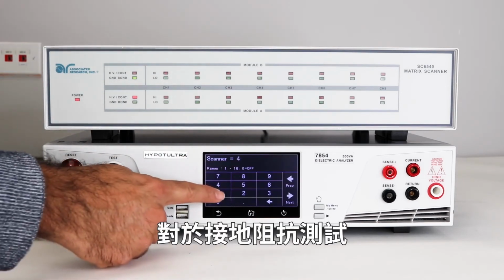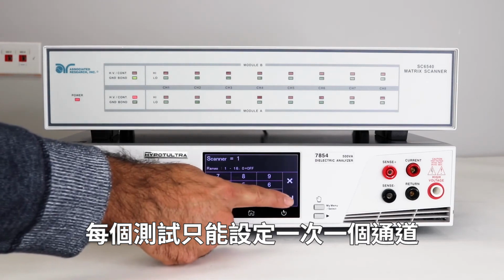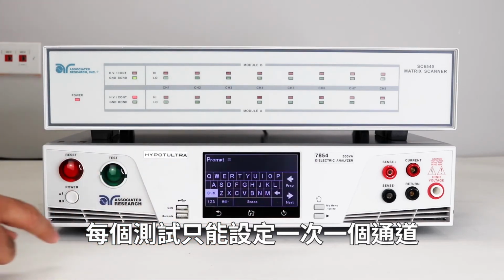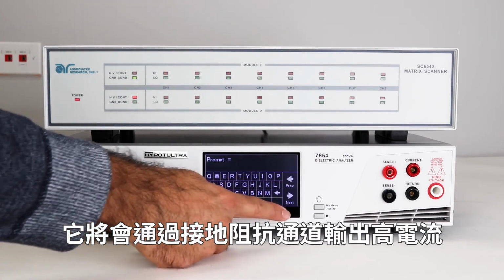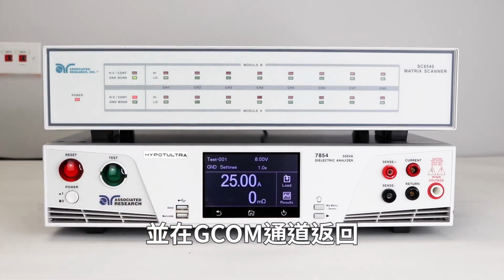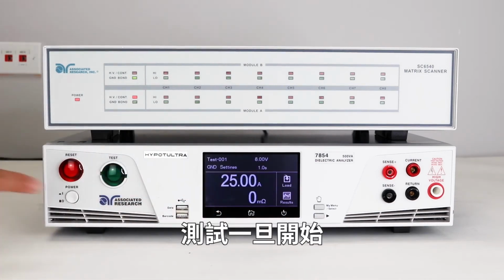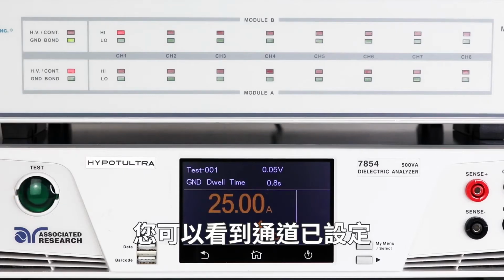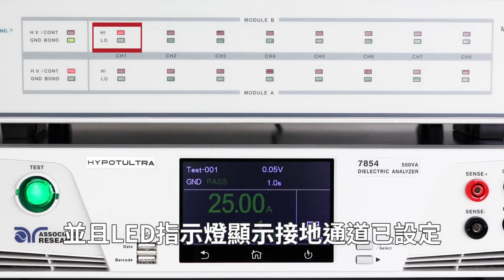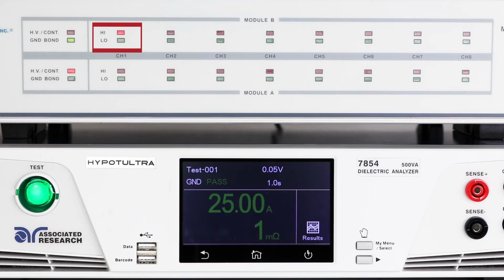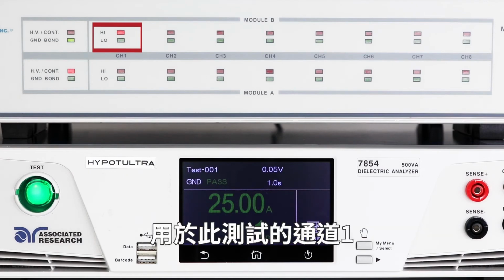For the ground bond test, you can only set an individual channel one time per test. It's going to output high current through the ground bond channel and return on the GCOM channel. Once the test is started, you can see the channel was set and that the LED indicator is showing you that ground channel is set for channel 1 for this test.